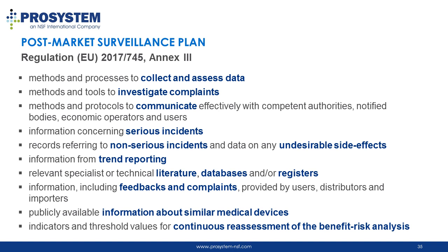For that, a post-market surveillance plan should be prepared and include important aspects such as how the data will be collected and assessed, investigation of complaints, protocol for communication, recording of serious and non-serious incidents, information from trend reporting, searches in the literature, databases, and registers, including similar devices, and a continuous reassessment of the benefit-risk analysis. Data collected following the post-market surveillance plan are potentially important clinical data to be considered in the clinical evaluation.